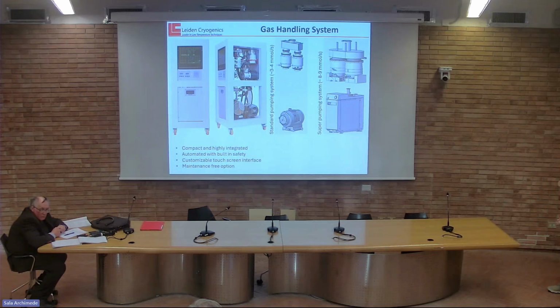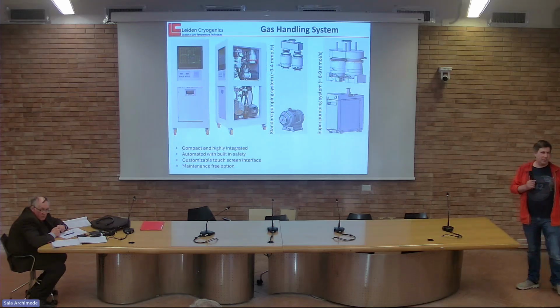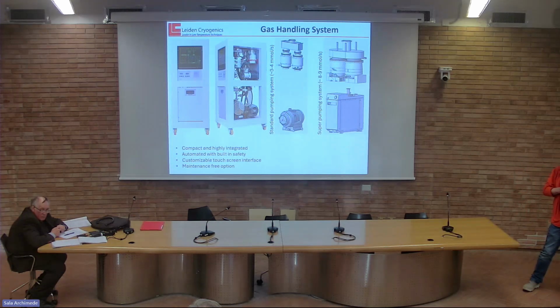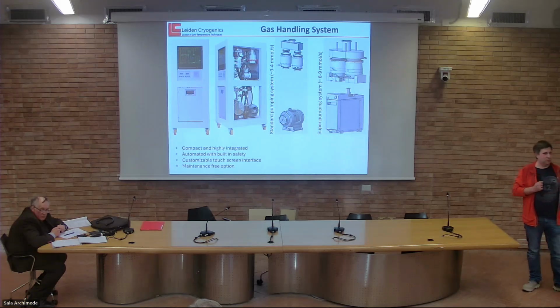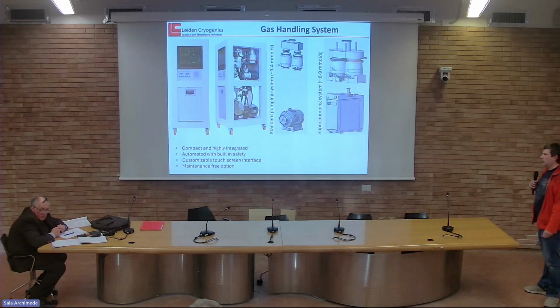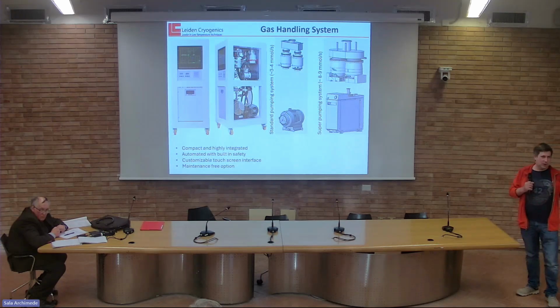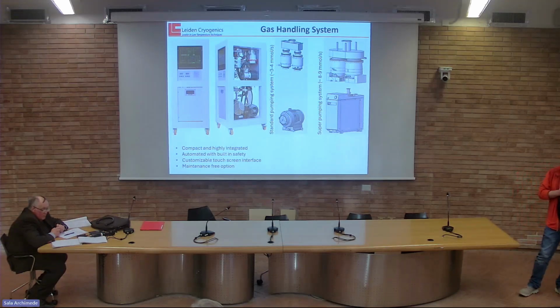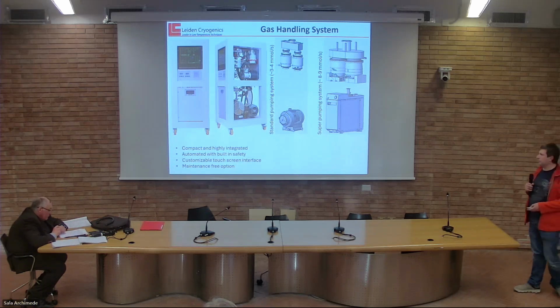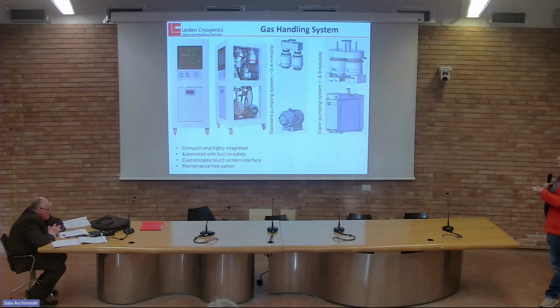It also has built-in safeties, so say your circulation circuit gets plugged, it will detect that the pressure is rising and open the valves and recover the mixture to save expensive helium-3. It also has a battery, so it will detect if there is an external power loss, and it will also open the valves. It cannot run the pump with the small battery, but it can open the valves so the helium can escape if there is a power loss. And we have an option of maintenance-free pumps, like magnetically levitated turbos and multi-stage roots pumps, which don't require any maintenance at all and can run for years continuously without any service.